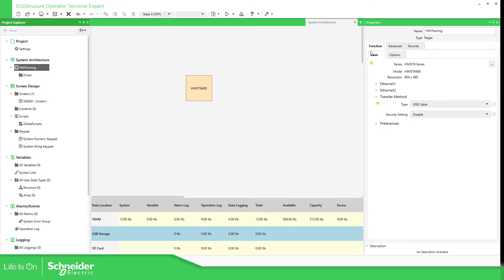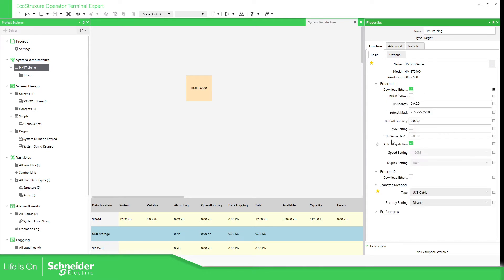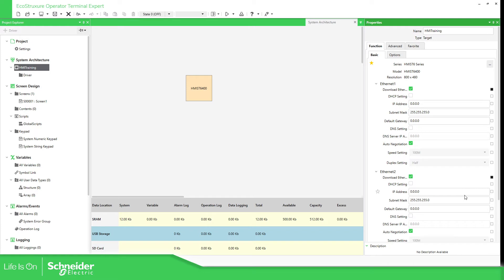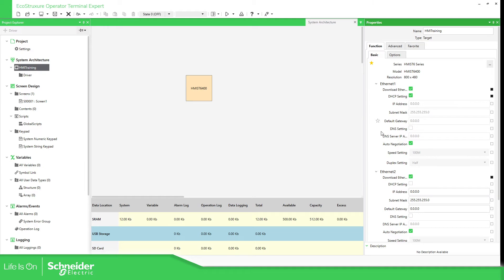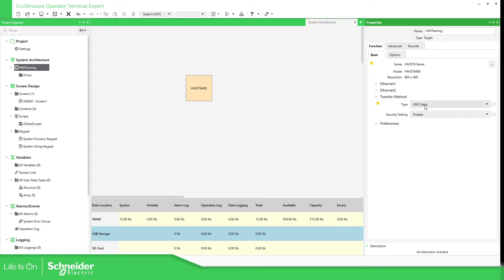If we go to Function Basic we can see here the configuration of the ports of the HMI. This HMI has two different ports so you have two Ethernet ports. To make it easy we're going to select the DHCP so we can have direct access. Our router will give us the IP configuration of the network. And then at the bottom here we can select the transfer method USB.